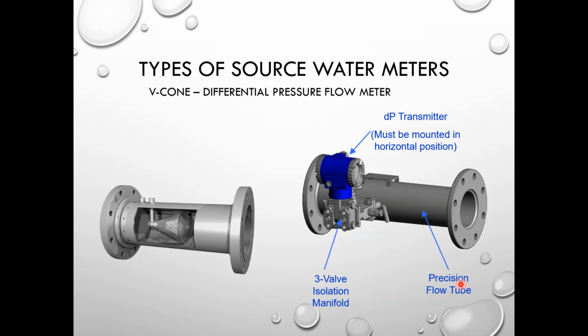The other types of meters that aren't as well known are orifice plates, V-cones, differential pressure. I call these differential pressure flow meters. And these are flow tubes that are manufactured, and you'll have an accurate ID dimension that's measured and a flange where it just bolts in. And there'll be a valve in here, a 3-valve isolation manifold, and then it goes to what we call a differential pressure transmitter, DPI indicators.